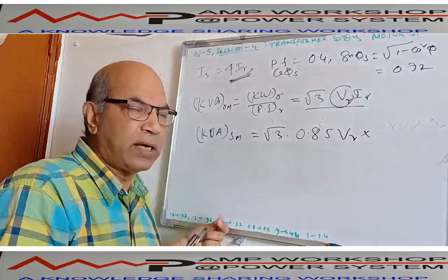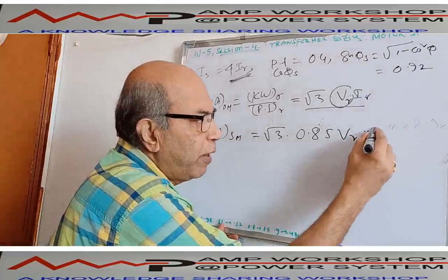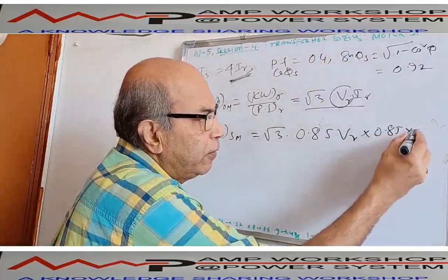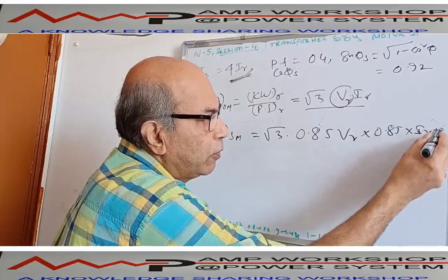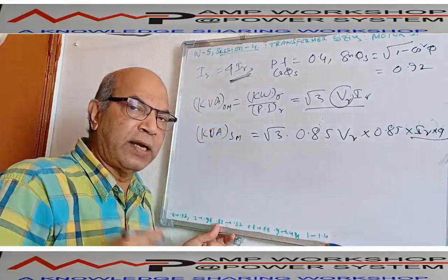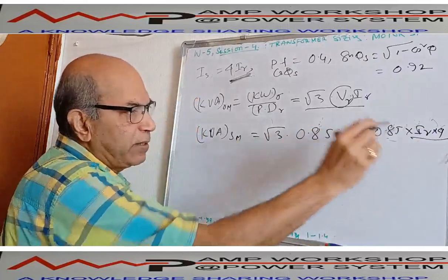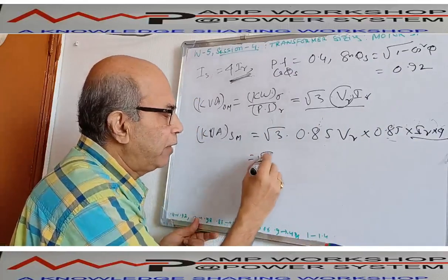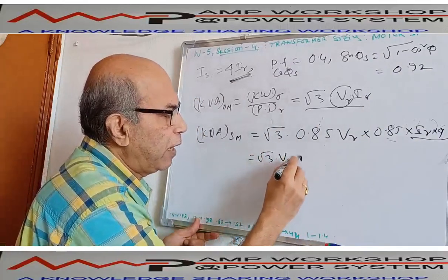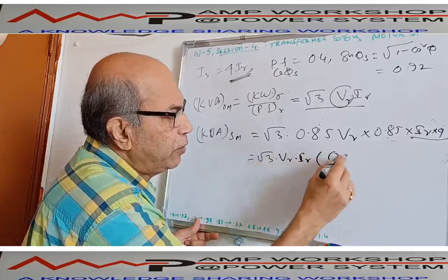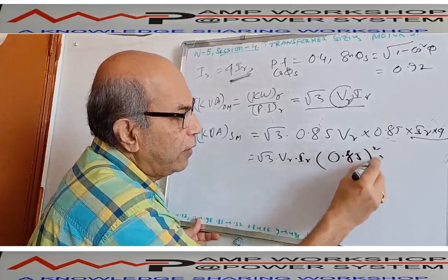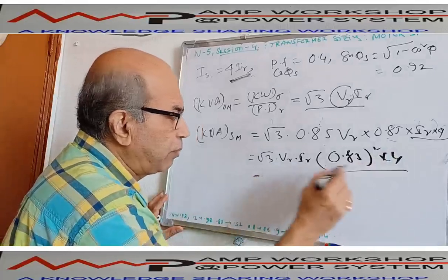Running current, actual starting current will be, we said 0.85 into IR into 4. We calculated 4IR is the starting current at 100% voltage; at 85% voltage it will be 0.85. So this will be a starting KVA. This is equal to, if we calculate, root 3 into VR into IR into 0.85 squared into 4.